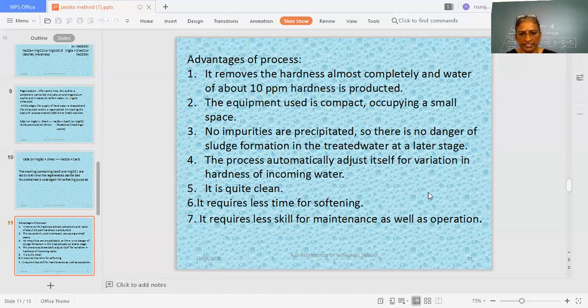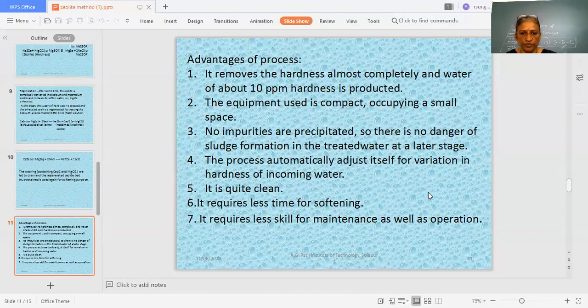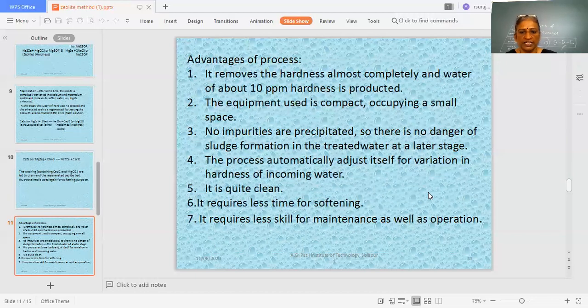This is relevant when compared to the lime-soda process, where large amounts of sludge are formed — but in the zeolite method only clear water is obtained. The process automatically adjusts itself for variations in hardness of incoming water, meaning any hardness level of water can be treated. It requires less time for softening and less skill for maintenance — there is no significant maintenance needed. So this is a very popular water softening procedure.